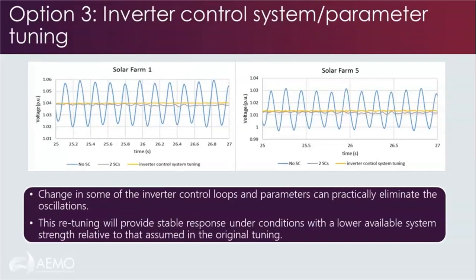Last but not least, the use of inverter tuning. In this case, we have overlaid the results from the previous option with two synchronous condensers, and what can be achieved with no synchronous condensers but with tuning of the inverter control system. We can see that the two responses are fairly similar, and the level of oscillations is negligible, especially with the use of inverter control system tuning.